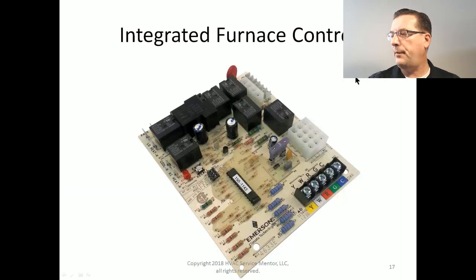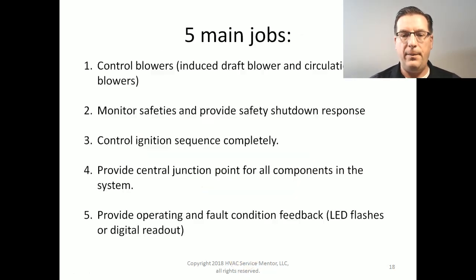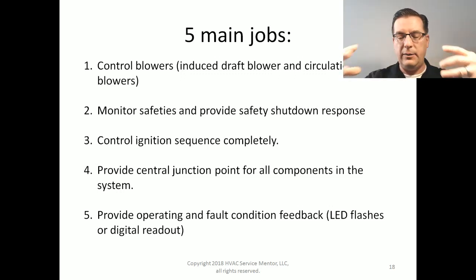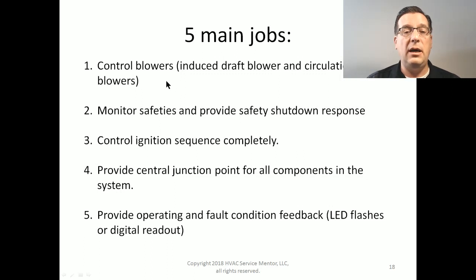Here we are. Let's take a quick look at an integrated furnace control. Here we have one. What is the main idea? We're going to take all these big things that I just covered and apply them to this integrated furnace control. What is the big idea? What are the loads it controls? Well, it controls a draft blower. It controls the circulation blowers. It controls the ignition sequence completely. It is also going to monitor safeties and provide a safety shutdown response. It's going to be a central junction point, and it's going to provide operating and fault condition feedback, such as LEDs or a digital readout.